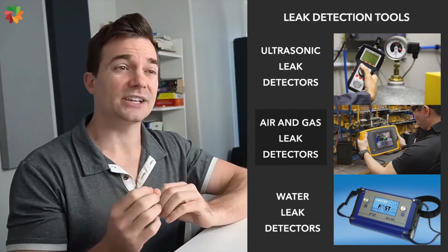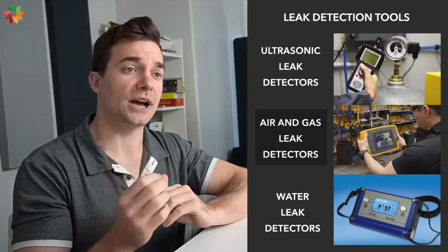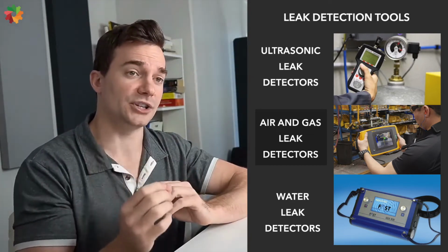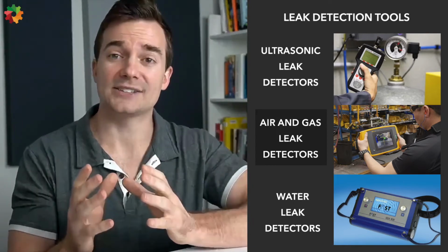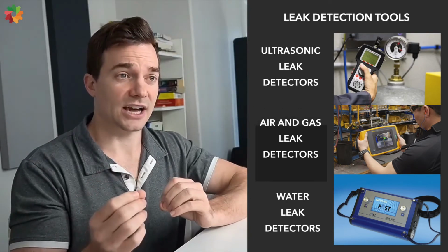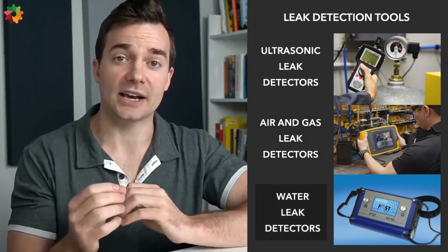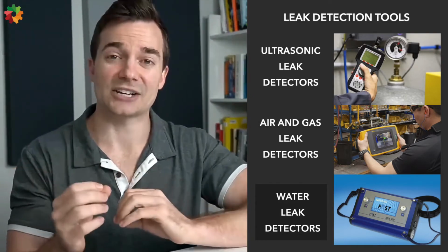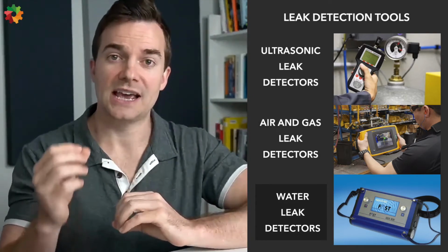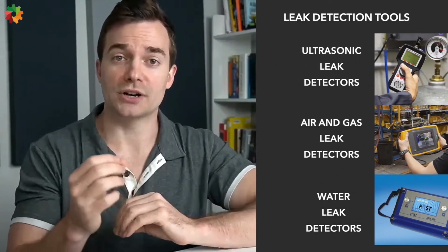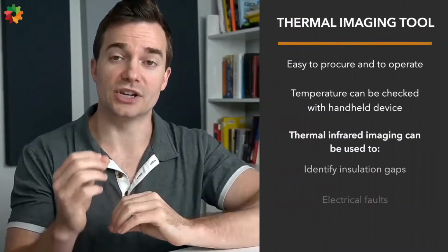In fact, air leaks can waste up to 30% of your compressed or vacuum air system's energy, according to the U.S. Department of Energy. Additionally, combustible gas leaks can also cause potential safety concerns. The third leak detector type is the water leak detector. These generally use technologies like acoustic or sonar-based leak detection or secondary detection methods, such as differential pressure and flow measurements. Thermal imagery is another sort of tool used in an industrial setting.